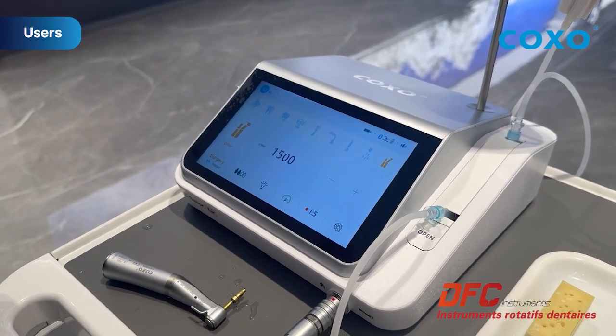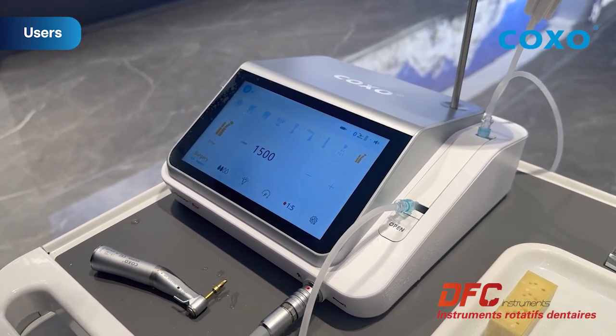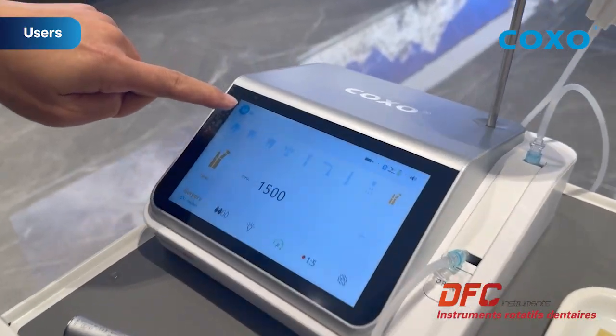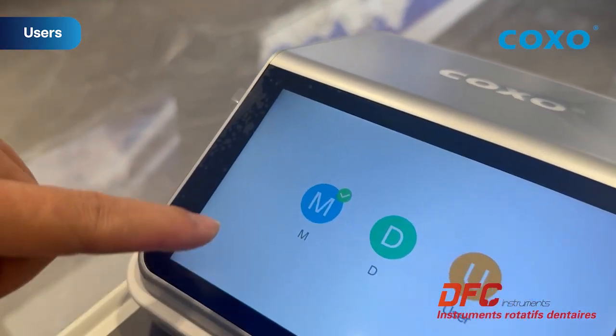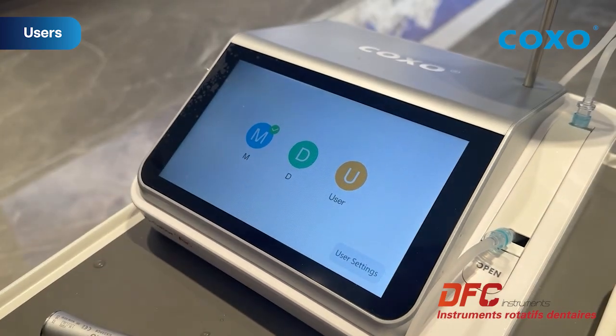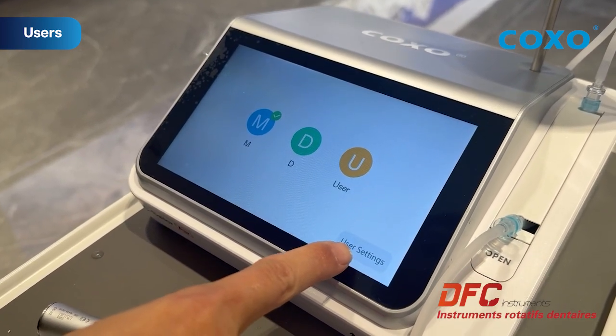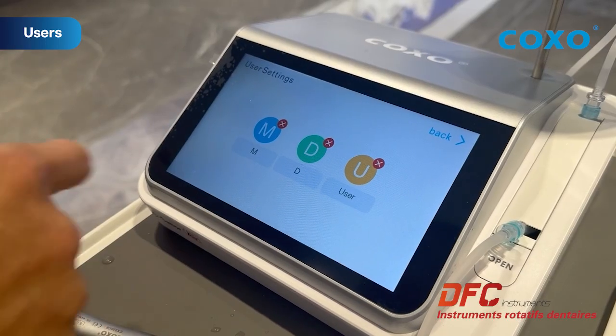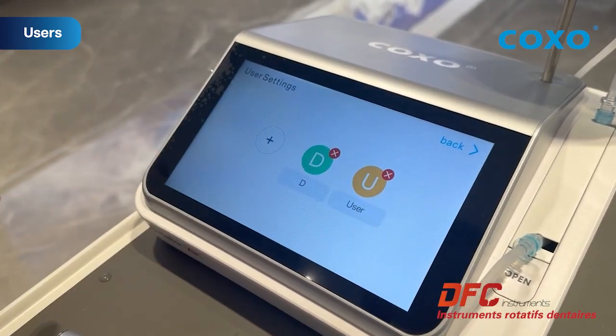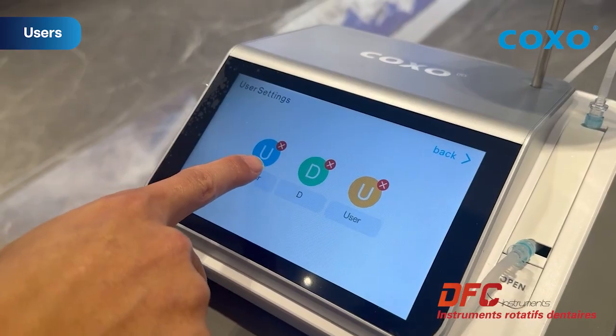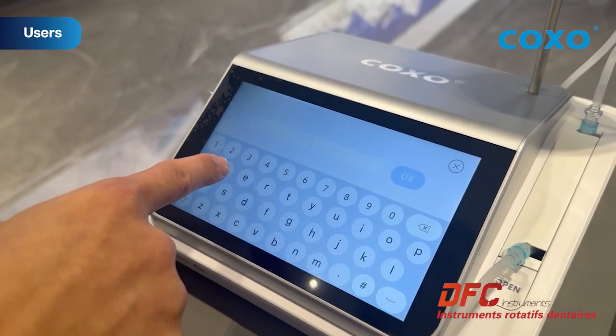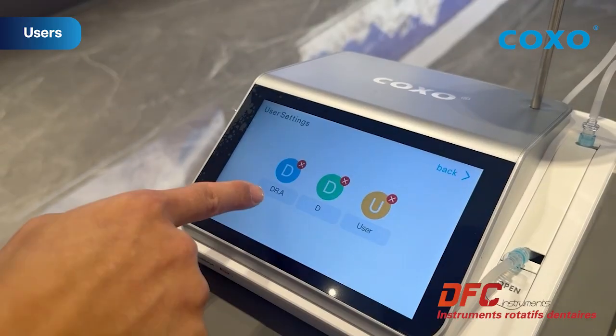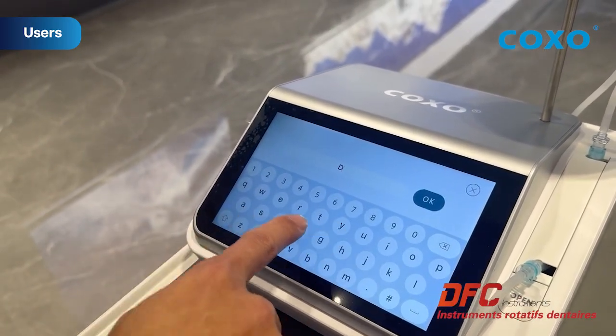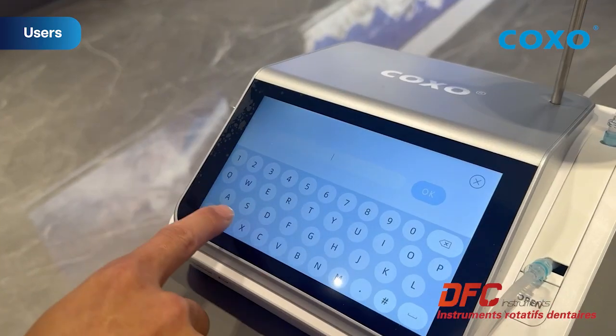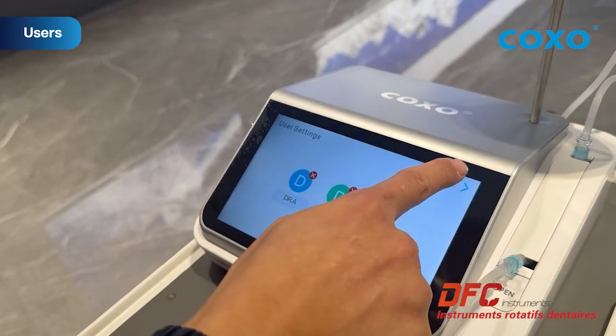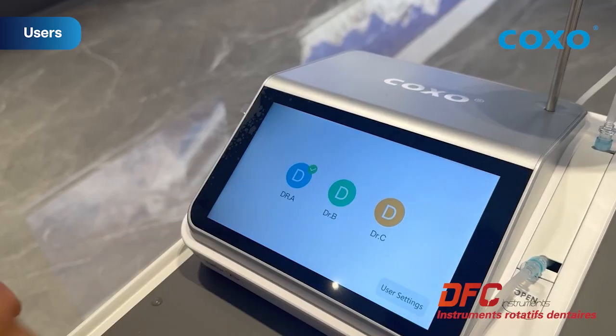The device supports up to 3 user profiles, each storing custom settings for implant and surgery modes. To change or modify the profile, you must select it at the top left of the interface. The device can save a maximum of 3 profiles. Select user settings to modify or delete profiles. Here, you delete the profile. You can thus create a new one. By selecting the text under the icon, you access the text interface to enter the profile name. Once the profiles are modified, you can save them and return to the main menu to select the desired profile.